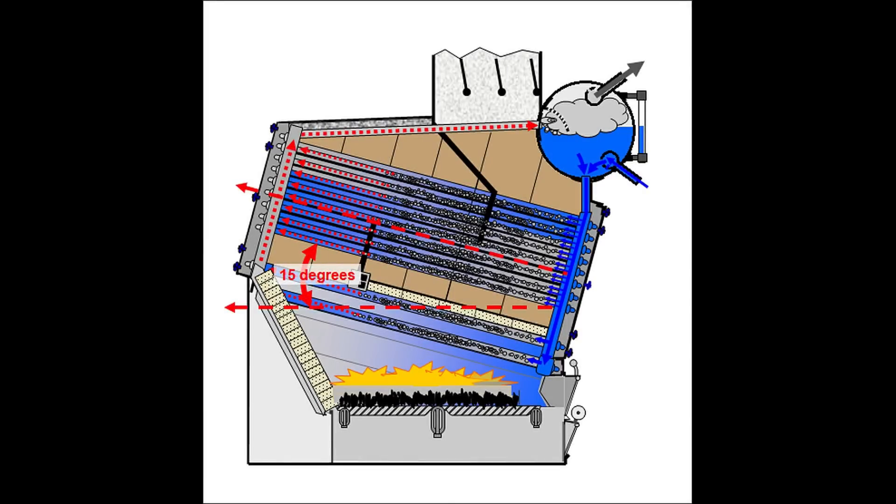There's one last thing to notice about all of the tubes in the water jackets. All are tilted at a 15 degree upward angle from front to rear. This created the lift needed to force steam bubbles to rise from the lower headers containing incoming water to rear headers where steam is collected and sent to the steam water drum.